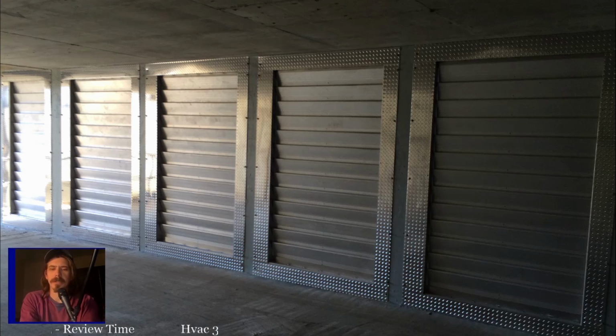It can just be basically a strip of metal that's pretty springy. There are two different metals there that expand and contract at different temperatures, so that as power's passing through it, if it's an overload, or as it heats up, the one metal expands and breaks the switch, and then when it cools down, it closes the switch again. That's basically how a lot of your breakers work, with that bimetal element in there that just opens and closes. It's two different metals, and I forget what they are, but it sits in a normally closed and a normally open position.